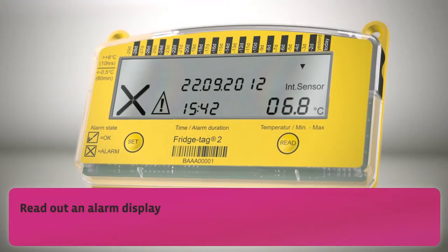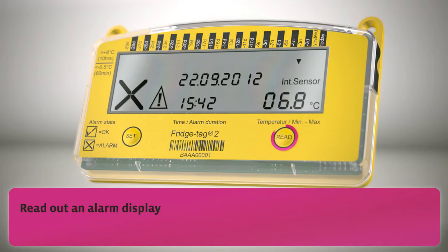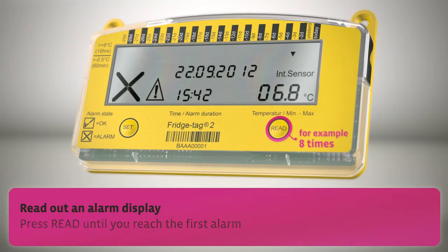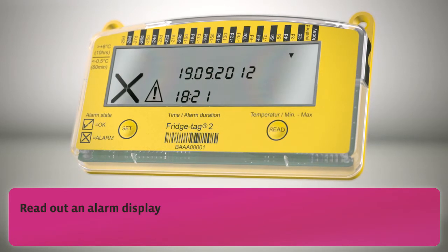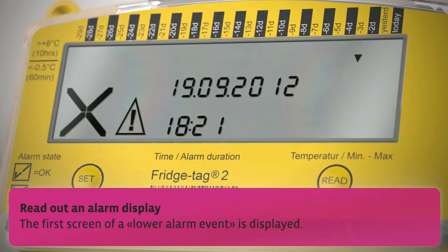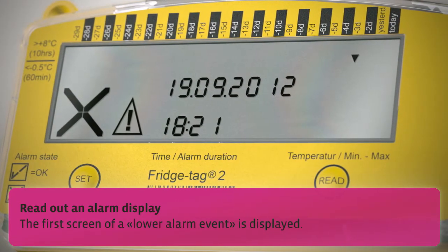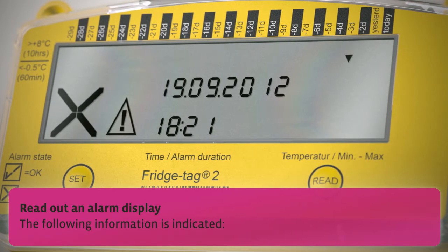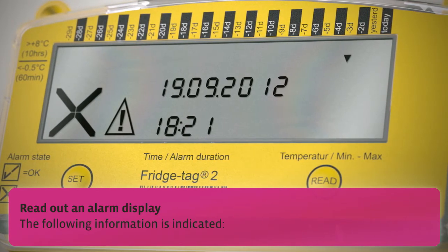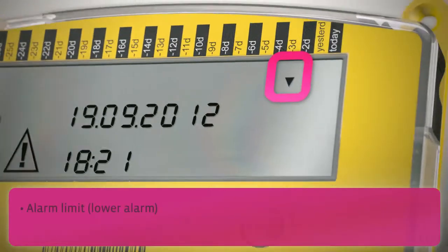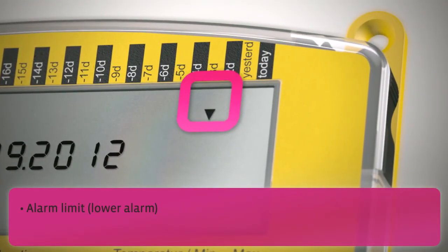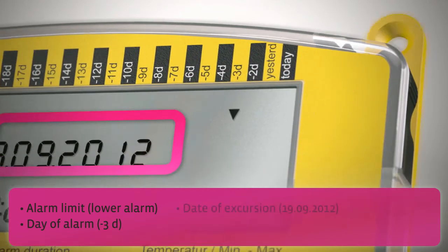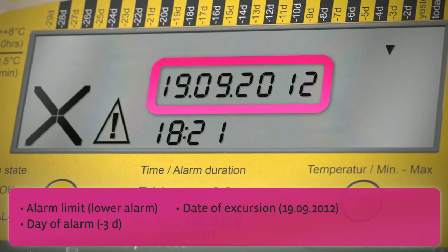Read out an alarm display. Press read until you reach the first alarm. The first screen of a lower alarm event is displayed. The following information is indicated: alarm limit, day of alarm, date of excursion, and time of excursion.